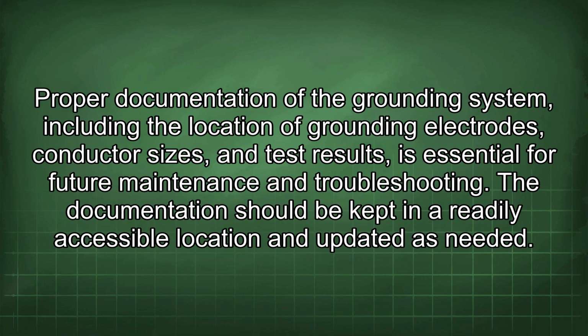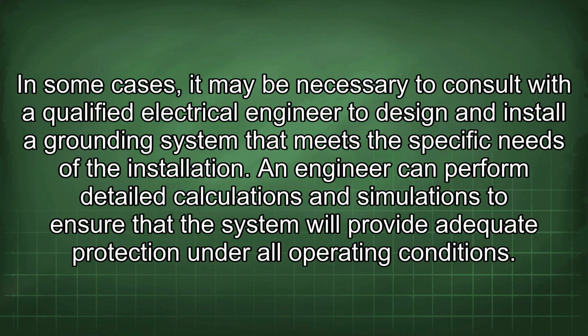Proper documentation of the grounding system, including the location of grounding electrodes, conductor sizes, and test results, is essential for future maintenance and troubleshooting. The documentation should be kept in a readily accessible location and updated as needed. In some cases, it may be necessary to consult with a qualified electrical engineer to design and install a grounding system that meets the specific needs of the installation.